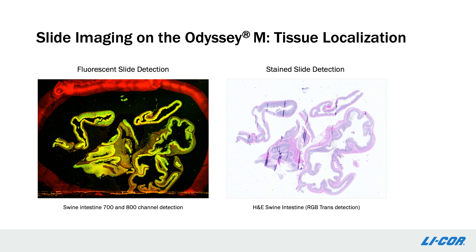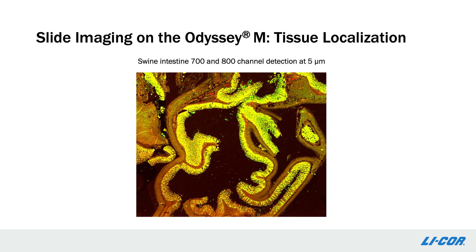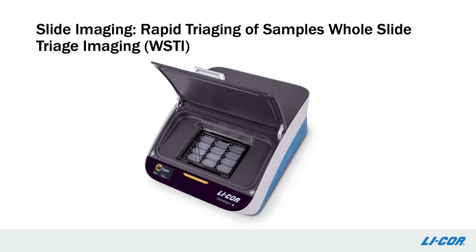Slides can be imaged in fluorescent and transillumination channels on Odyssey-M. Here, images of swine intestine stained with either target-specific antibodies in the 700 and 800 fluorescent channels or stained with H&E are shown. These images are taken at 5 micron resolution, which is high enough to see tissue localization between two images. This zoomed-in portion of the 5 micron image demonstrates the degree of detail Odyssey-M can provide — we see well-resolved intestinal structure. In addition, the line scanner on Odyssey-M allows rapid scanning: it takes about 30 minutes to image 12 slides in one channel, meaning large sets of slides can be quickly scanned and triaged to determine which slides should be taken on to higher-resolution microscopy.